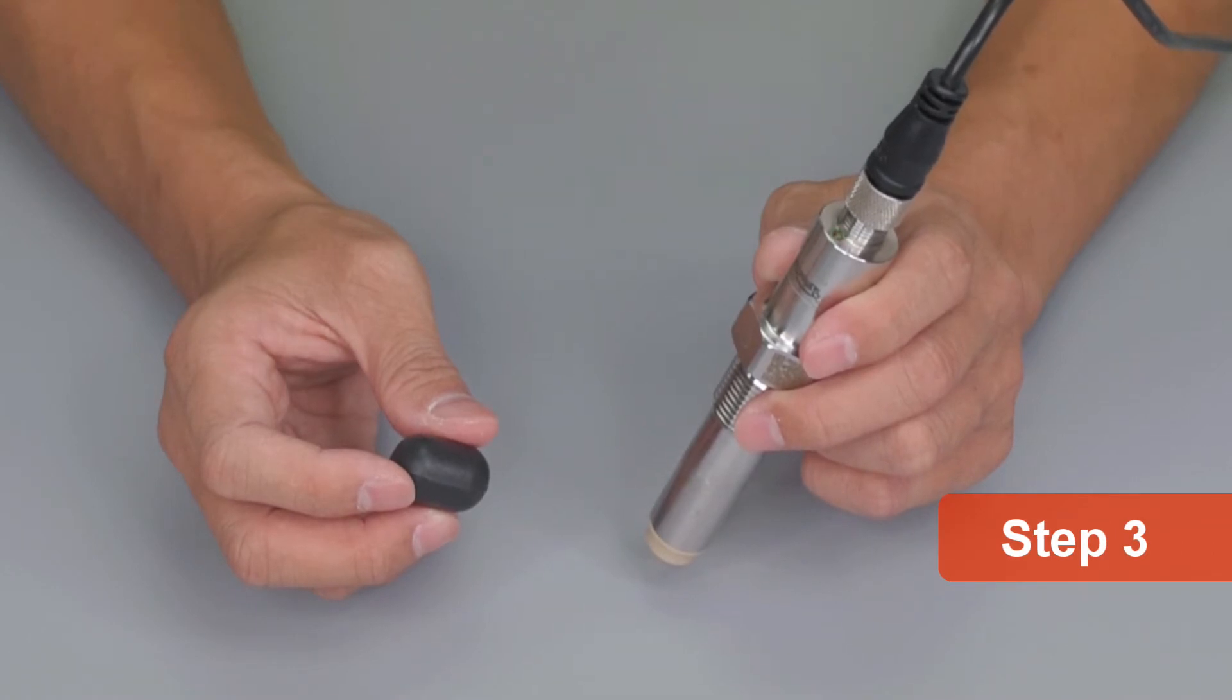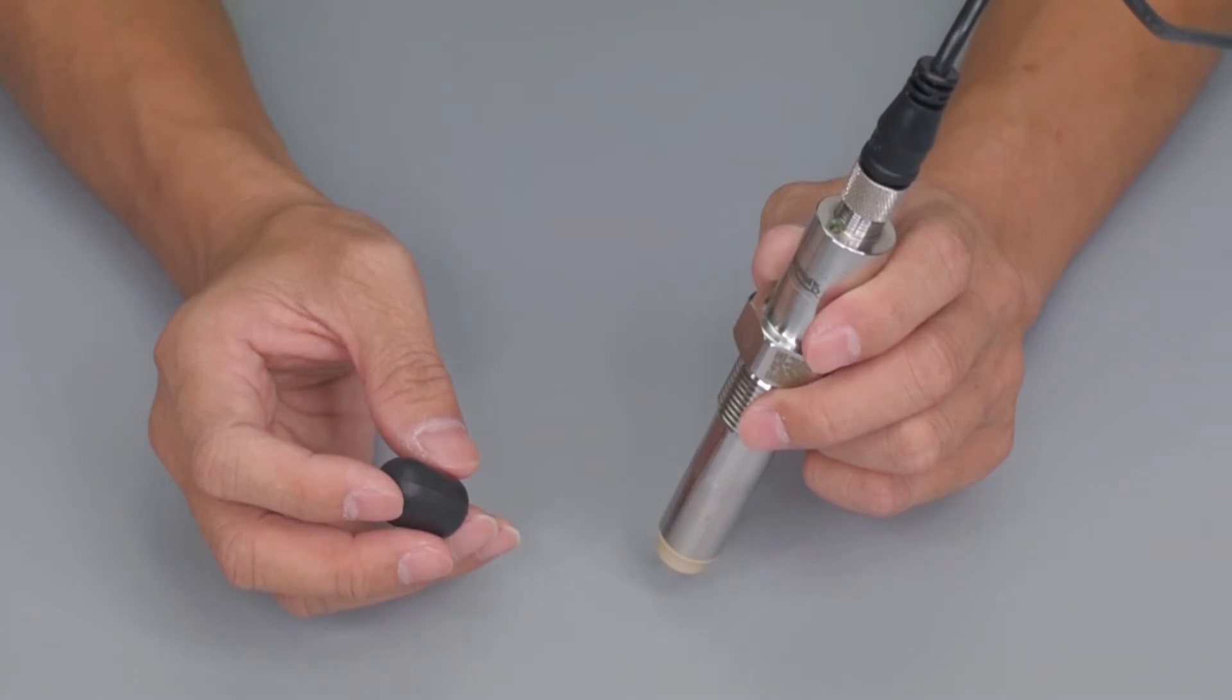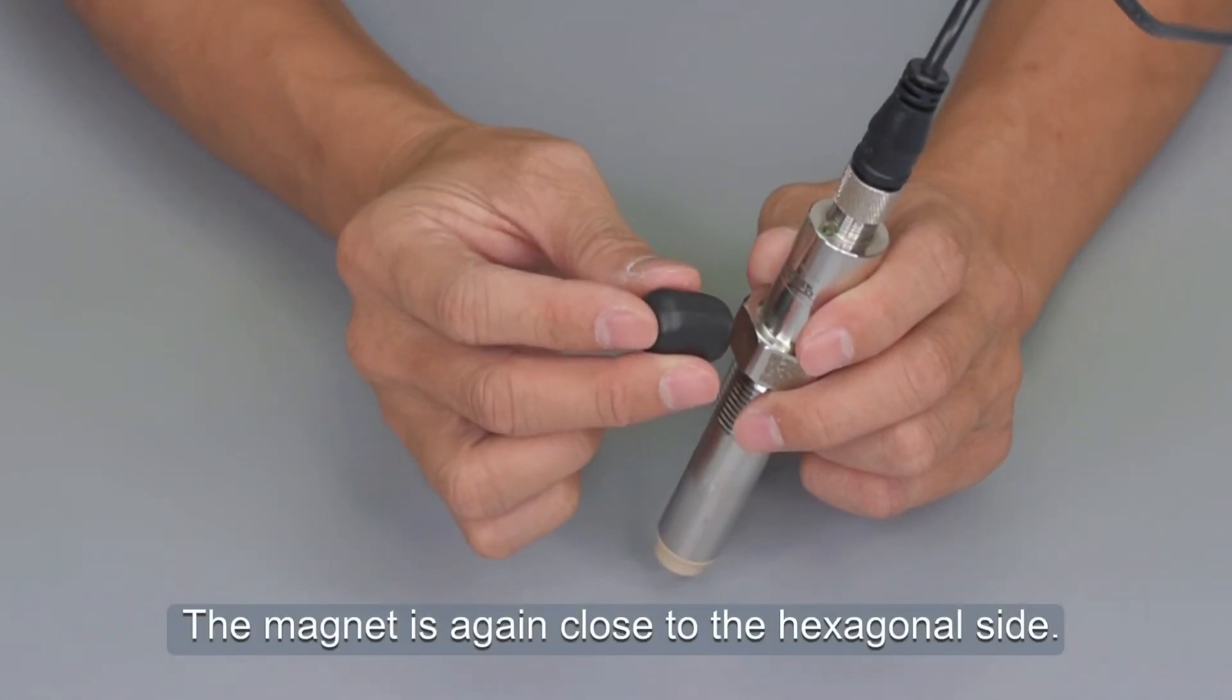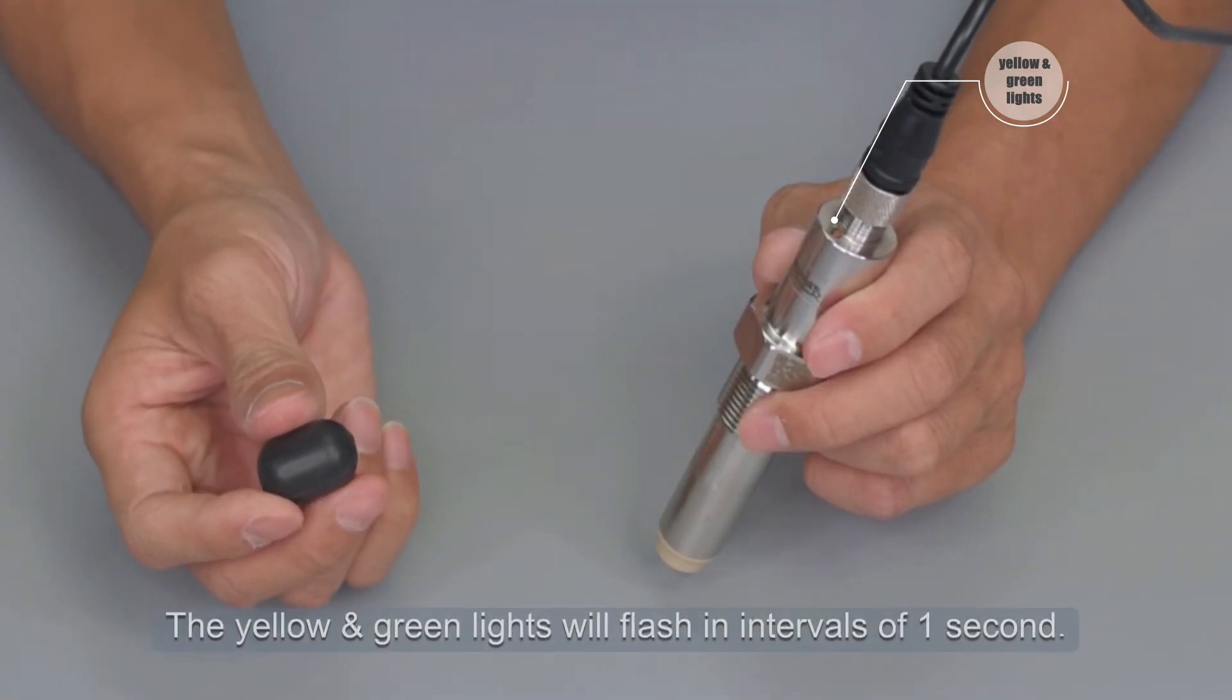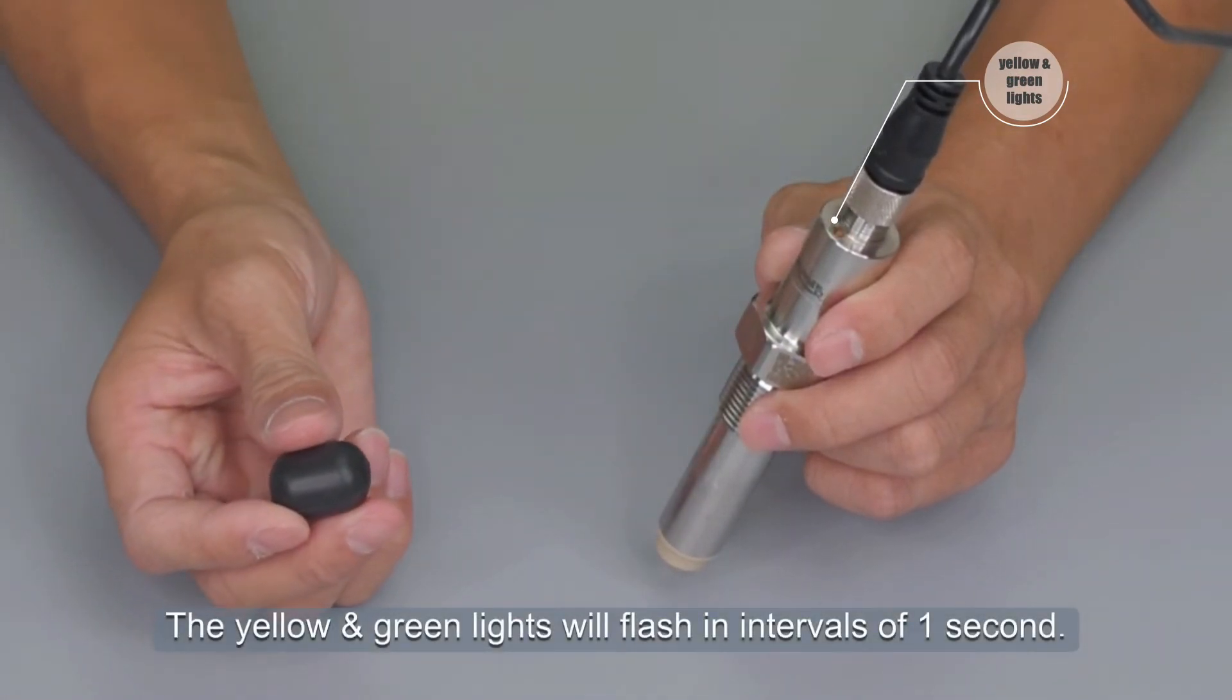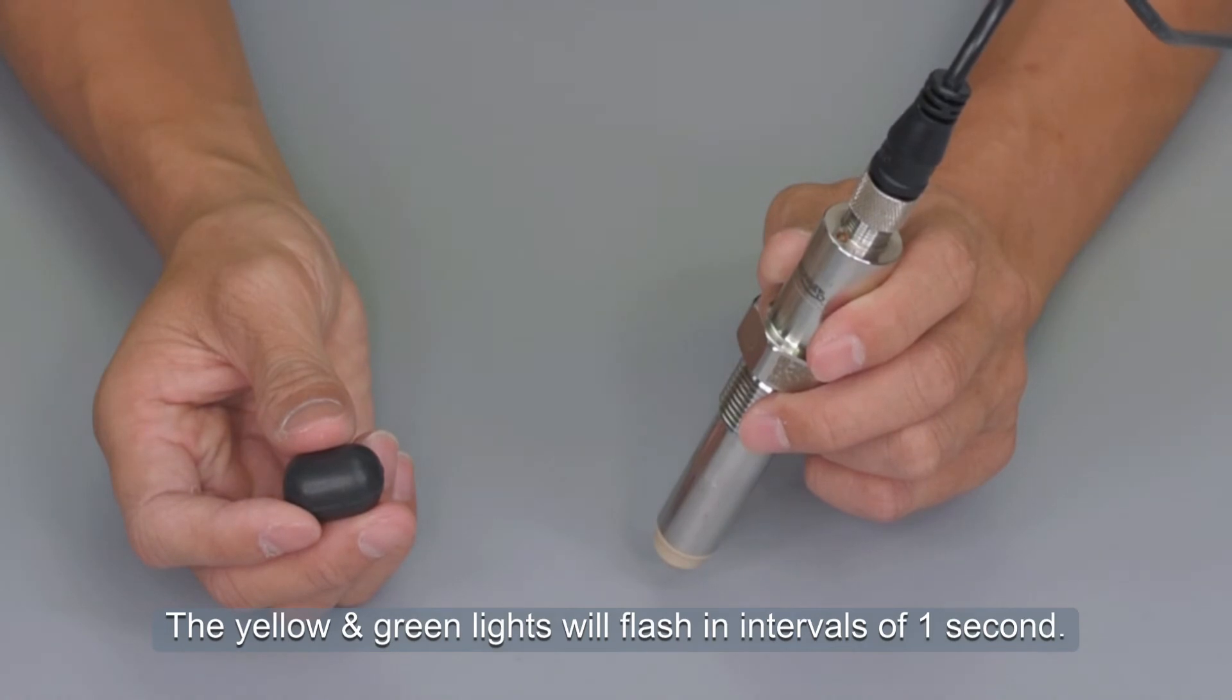Step 3. The probe must not touch any materials. The magnet is again close to the hexagonal side. Move the magnet away after 1 second. The yellow and green lights will flash in an interval of 1 second. At this time, the impedance measurement sensor will not be in contact with the materials.